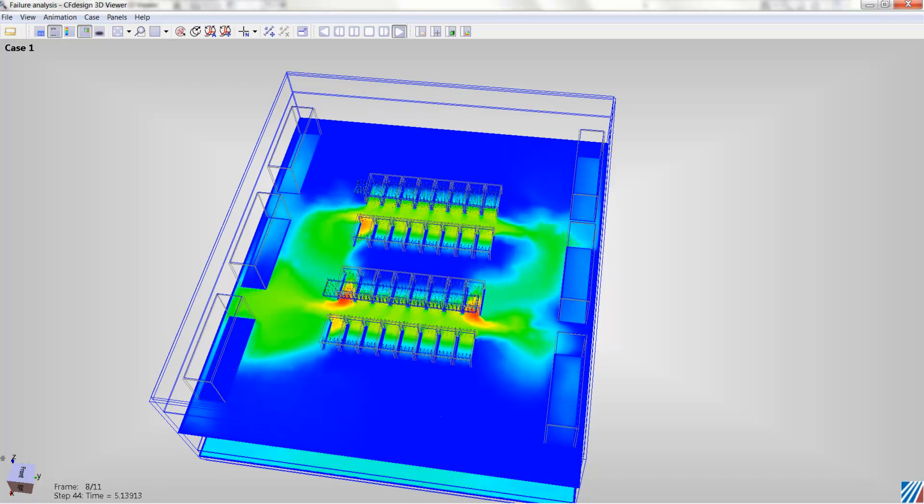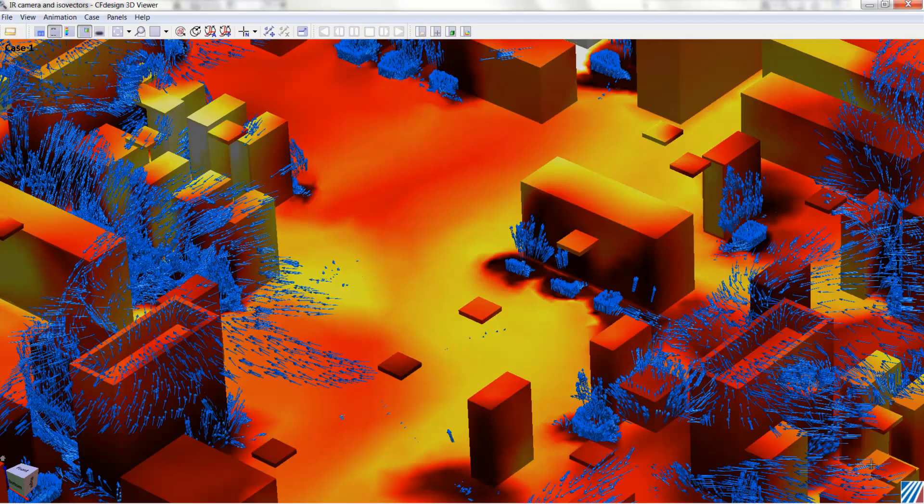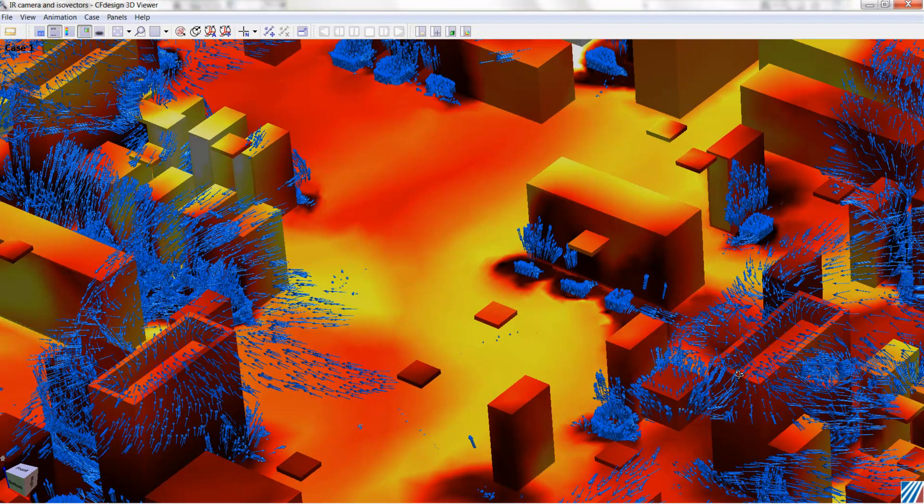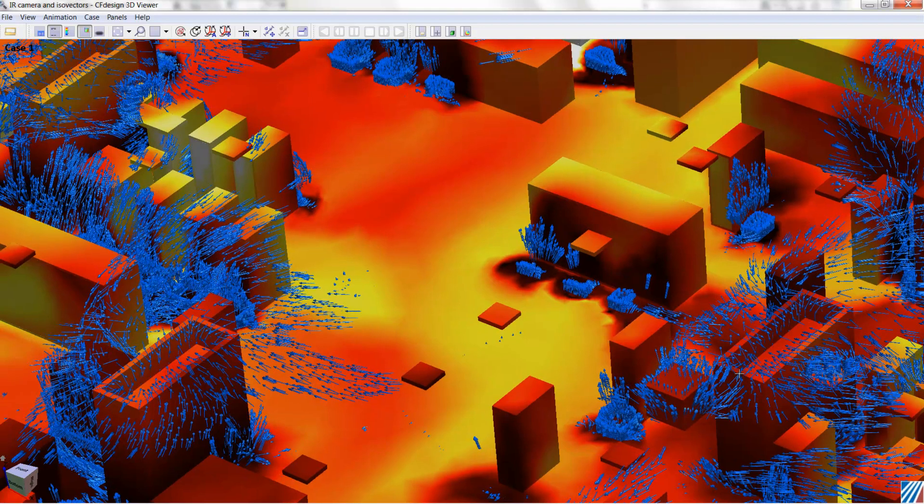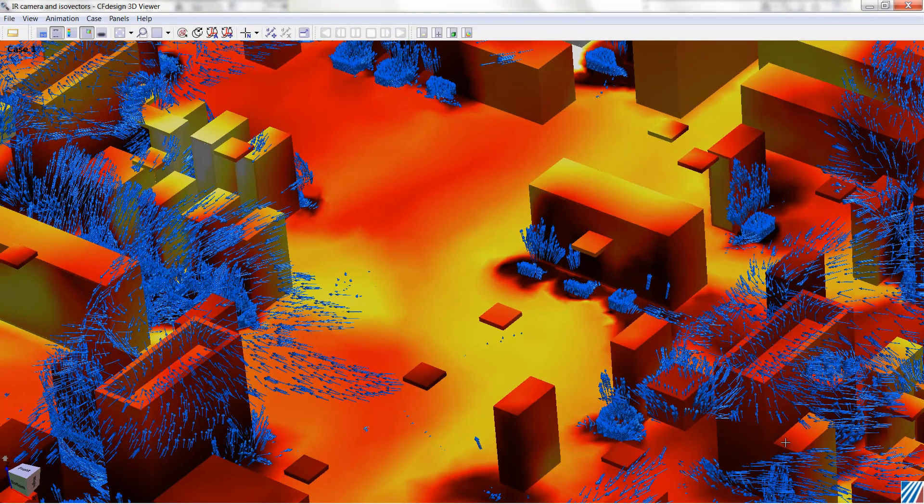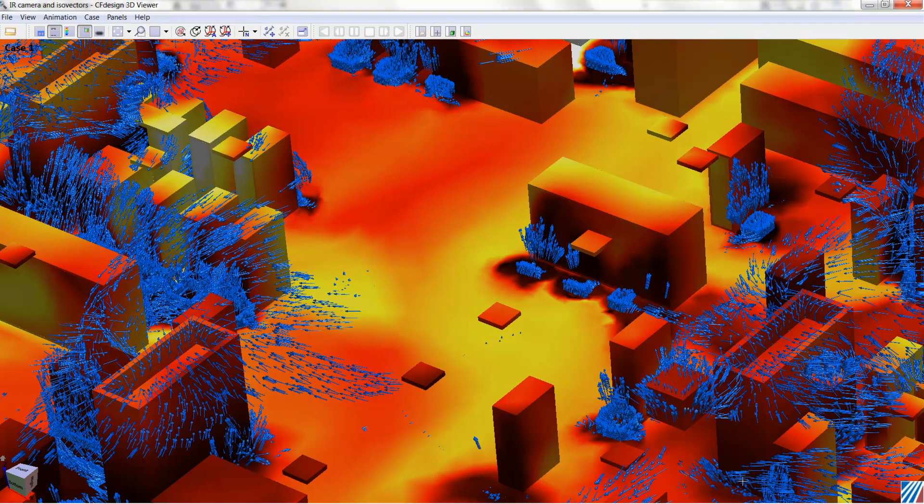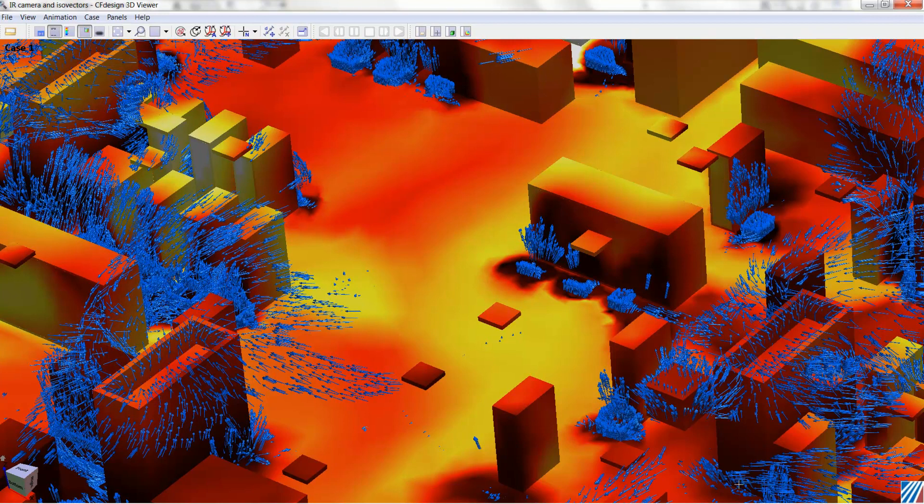Here is a final example we see above four thermal imaging and the isovectors. The isovectors show the airflow, so we can find areas, again, where air recirculates or stagnates. And the thermal camera gives us an infrared picture or snapshot of the thermal performance of the data center.